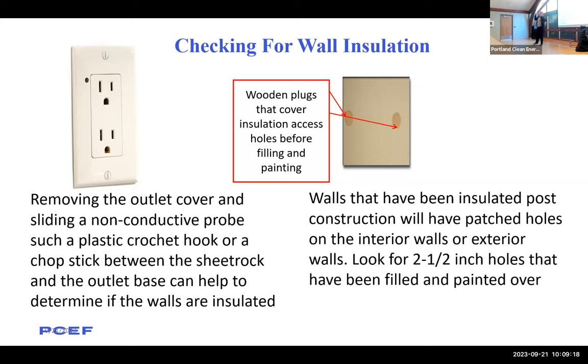Okay. So gas furnaces blow lots of nice hot air, and they can make people comfortable even with cold surfaces surrounding. We don't want cold surfaces surrounding our customers. We want warmer surfaces. An uninsulated wall is a cold surface in the wintertime. So please, I don't know the rules to your programs, but if you do have the opportunity to air seal and weatherize that house first, your customers are going to be a lot happier with heat pumps.